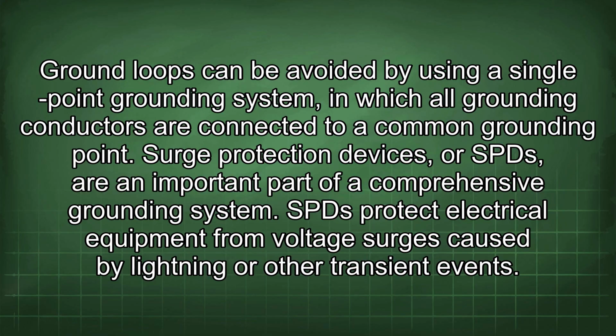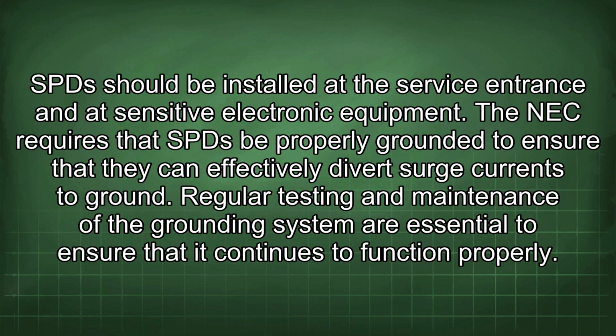Surge protection devices, or SPDs, are an important part of a comprehensive grounding system. SPDs protect electrical equipment from voltage surges caused by lightning or other transient events. SPDs should be installed at the service entrance and at sensitive electronic equipment. The NEC requires that SPDs be properly grounded to ensure that they can effectively divert surge currents to ground.